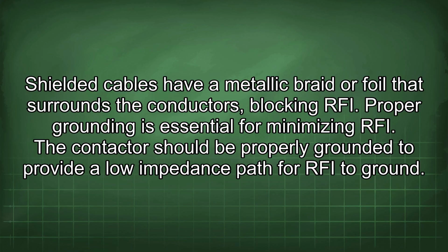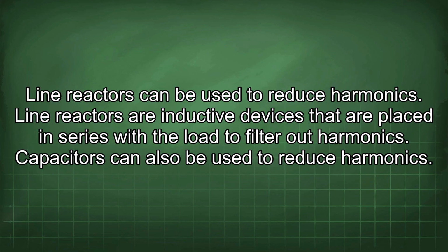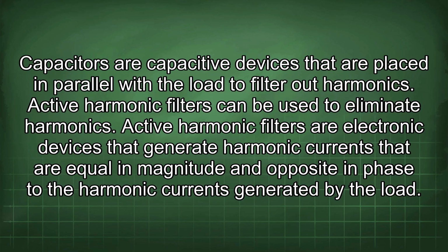Proper grounding is essential for minimizing RFI. A contactor should be properly grounded to provide a low impedance path for RFI to ground. Line reactors can be used to reduce harmonics. Line reactors are inductive devices that are placed in series with the load to filter out harmonics. Capacitors can also be used to reduce harmonics. Capacitors are capacitive devices that are placed in parallel with the load to filter out harmonics.